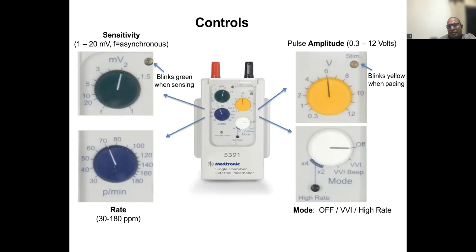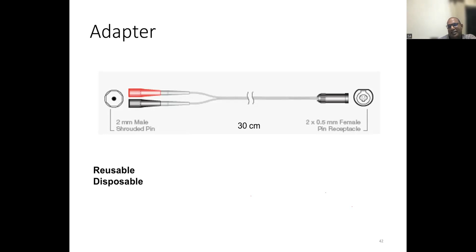Generally, we will have a compatible generator for a compatible pacemaker lead by way of an adapter specifically made for that particular combination. But occasionally, you might encounter in the cath lab a generator of one type and a pacemaker lead or temporary pacing wire of another type without the proper connection. That's a very bad situation to be in if you don't have the right adapter. Even after you take the trouble to implant the temporary pacing wire in the heart, if you can't connect it, you can't deliver any current. So before you even start accessing, make sure you have the right, compatible system at hand. Generally they are there, but people need to be cautious about it.